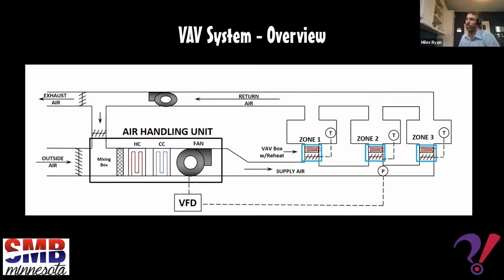Let's say zone 1 is calling for cooling. We would know it's calling for cooling because the thermostat would be reading a temperature above space temperature cooling set point, and it would be calling for more cooling. So how does it call for more cooling? Well, what it would do would increase the airflow set point for the VAV box. That is this little box in blue here.